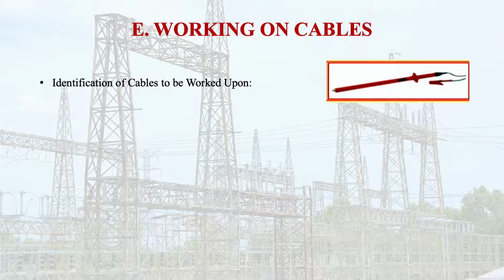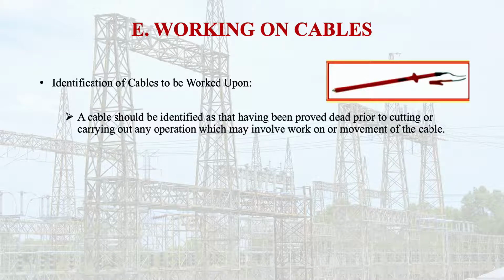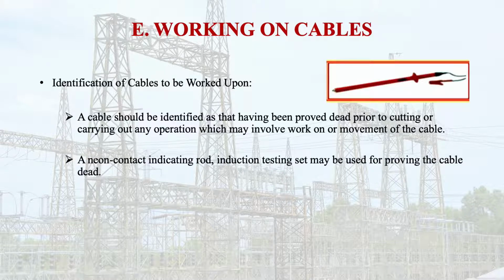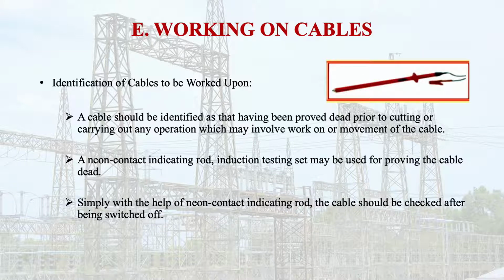Identification of cables to be worked upon. So first of all, we are discussing this. A cable should be identified as having been proved dead prior to cutting or carrying out any operation which may involve work on or movement of the cable. So it should be proved dead prior to any operation. A neon contact indicating rod or induction testing set may be used for proving the cable dead. Simply with the help of the neon contact indicating rod, the cable should be checked after being switched off.